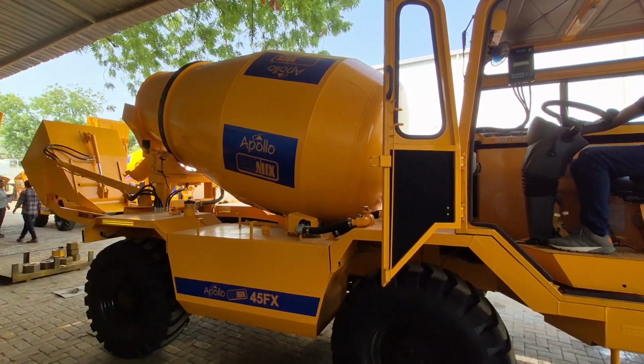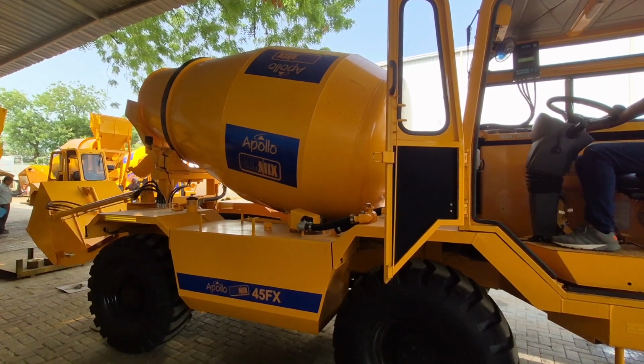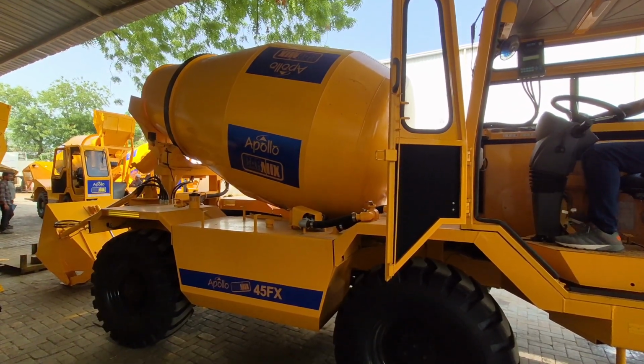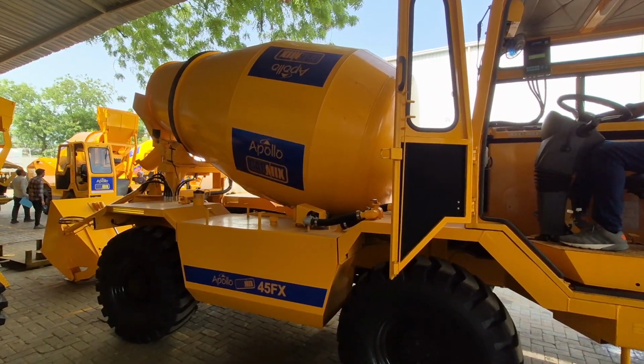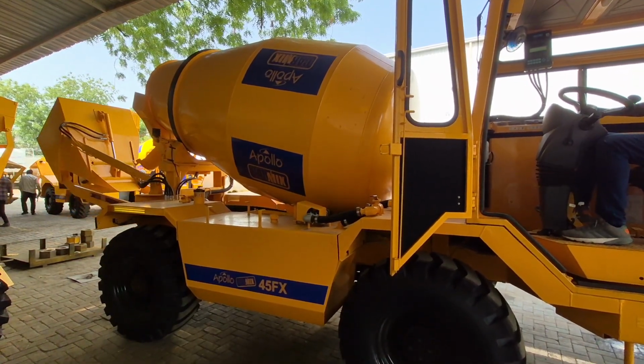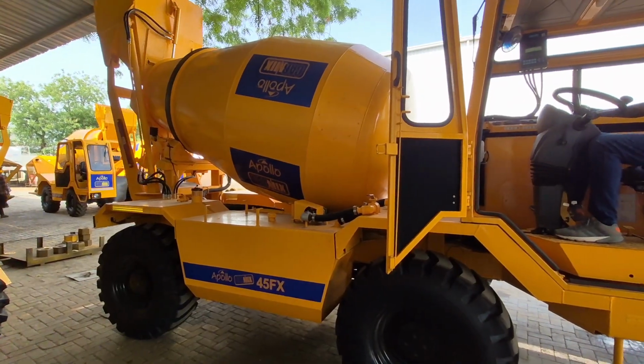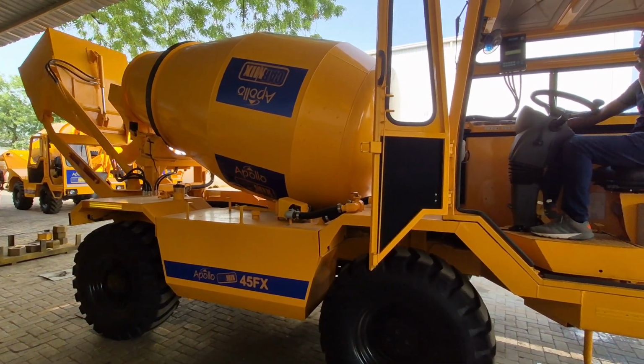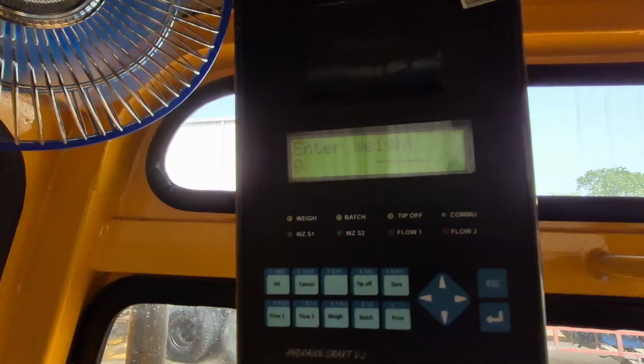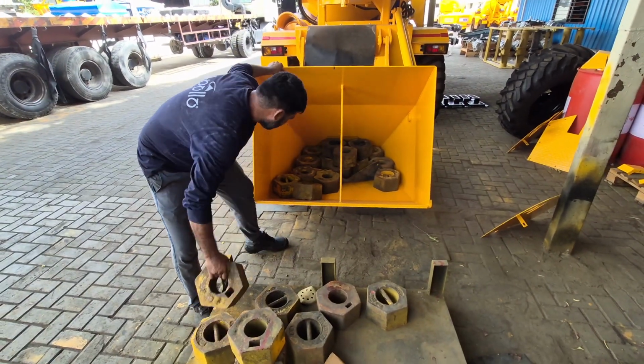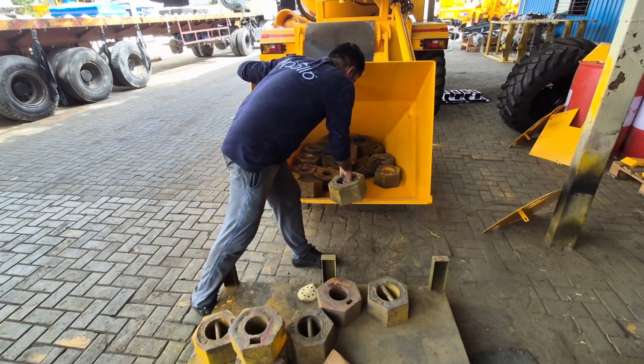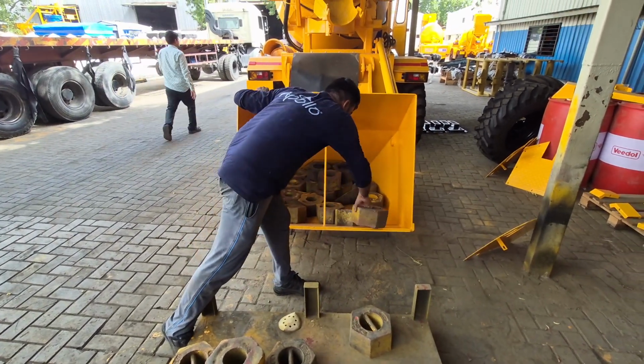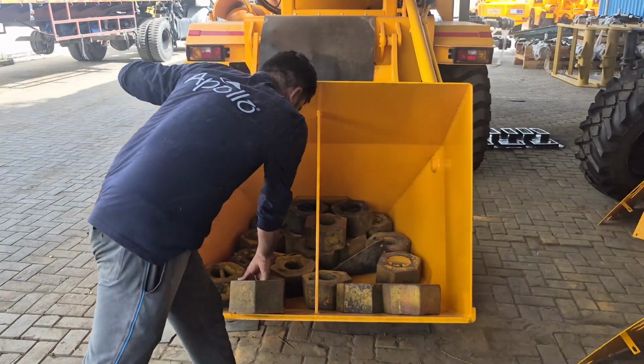So this is the process at every step, 100, 200, 300, 400 and 500, because we are going to do the calibration in 5 steps. Now you can see we are lifting up the bucket fast at high RPM, and the same, we will put down at a slow RPM. Now again we will add 100 kg more in the bucket. As you are aware that we lifted 300, now we are adding 100, so our weight will be 400 in the bucket. So we have to enter 400 on the screen and press enter.